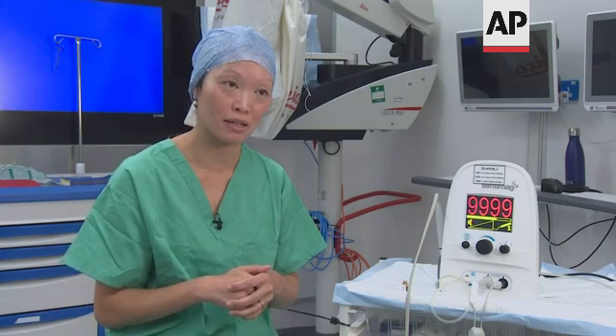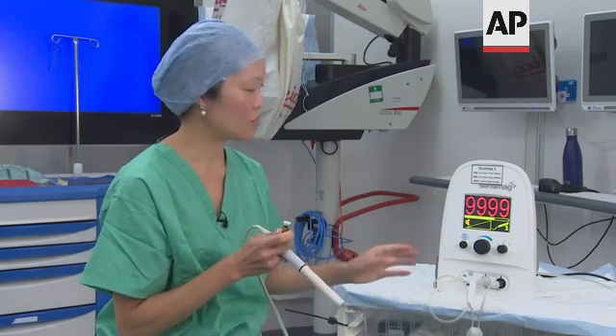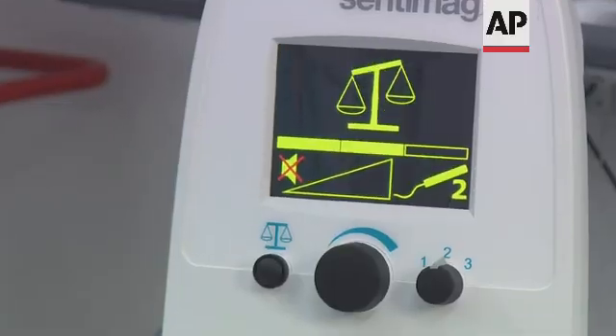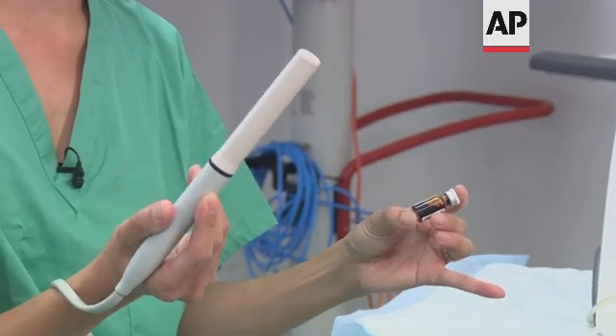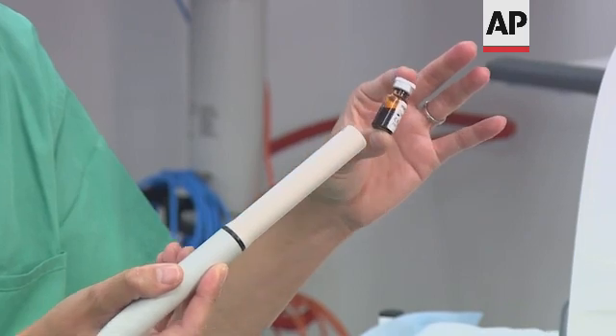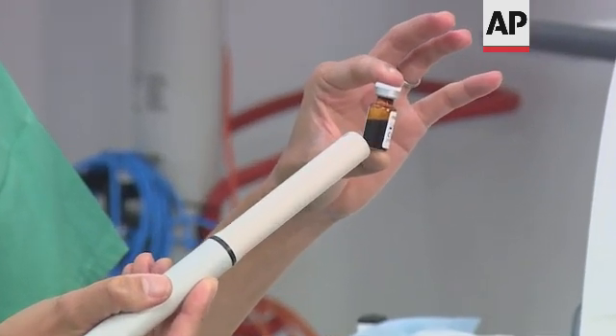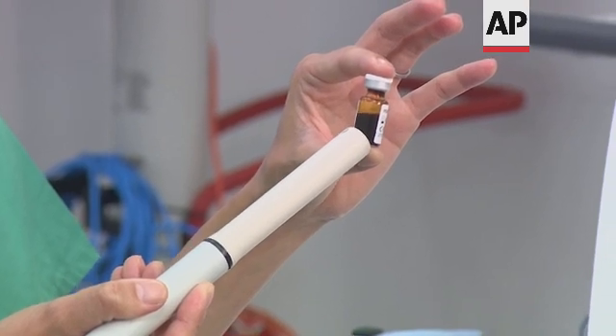I'm in control of using it — I can see a patient one day, give them the diagnosis, book them for surgery, and inject the MagTrace myself in the clinic. It also provides an audio signal: as the probe approaches the iron in the MagTrace, it magnetizes the iron and creates a signal, giving a very loud audio cue.